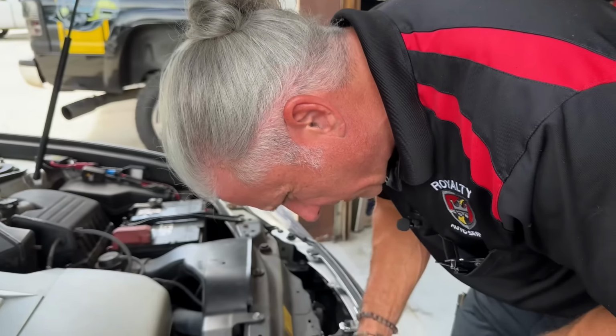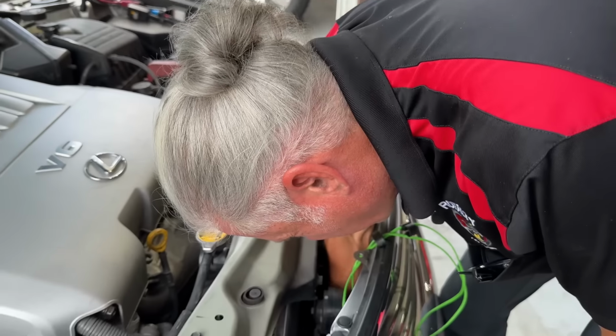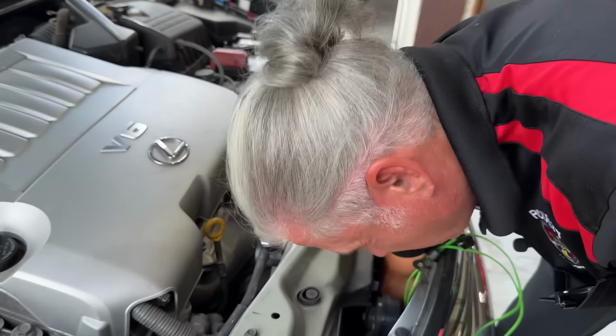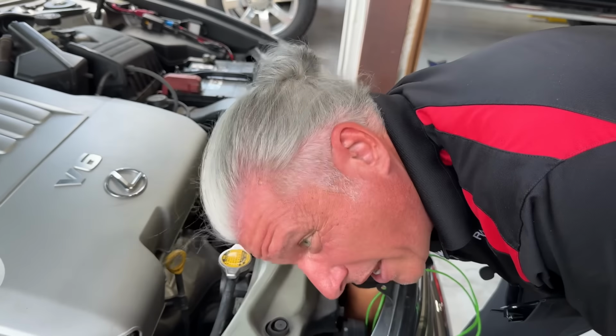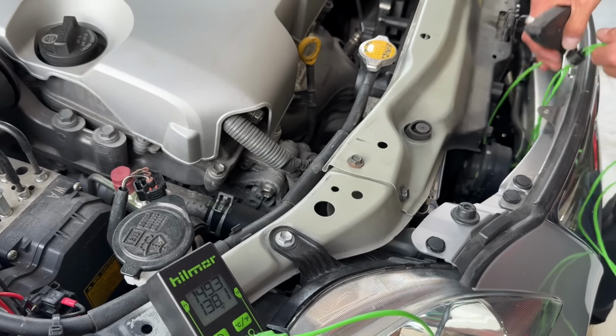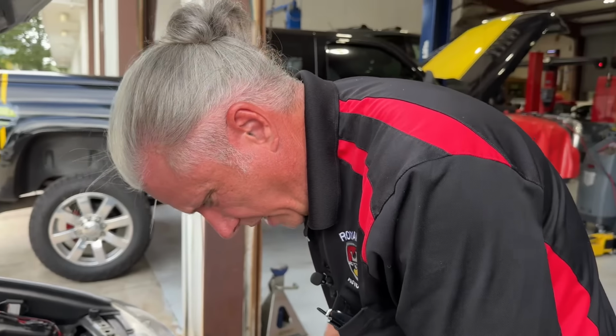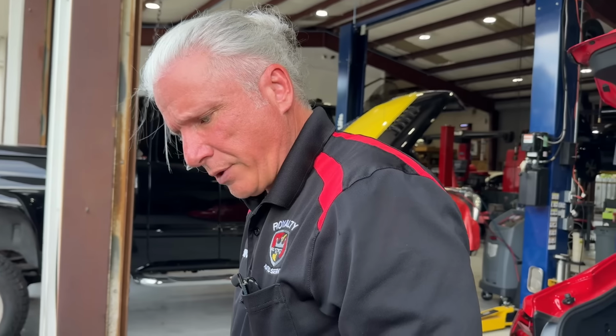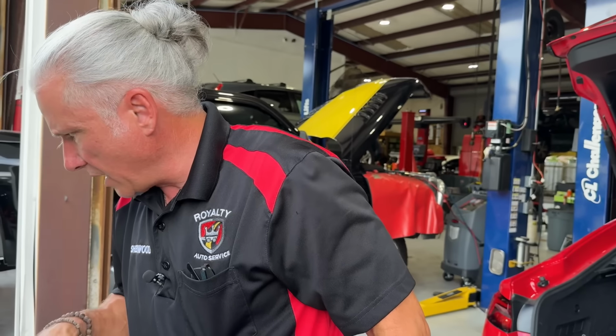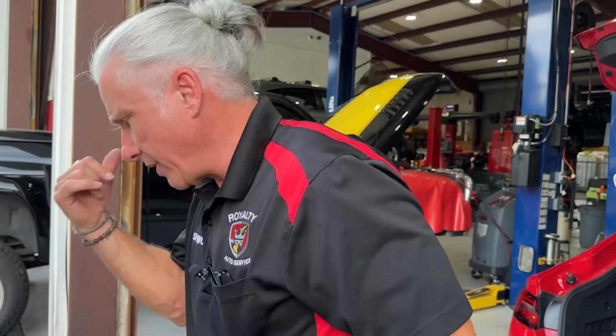Let's get these off. It was 138 when I pulled it off, and 160-something on the other side, so we were getting the temperature drop across there. Again, the better we can get that, the better it's going to cool, to a point. We don't want it more than 50. All right, let's go ahead, I want to get the machine on.